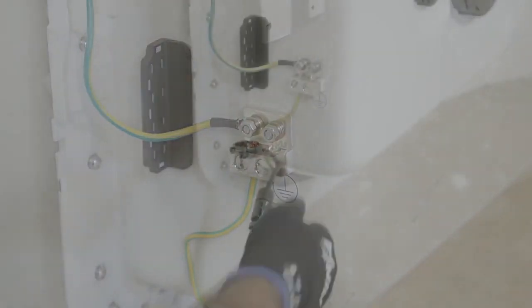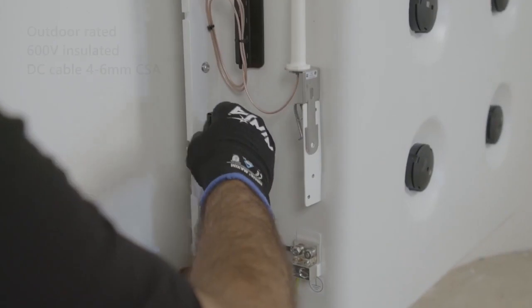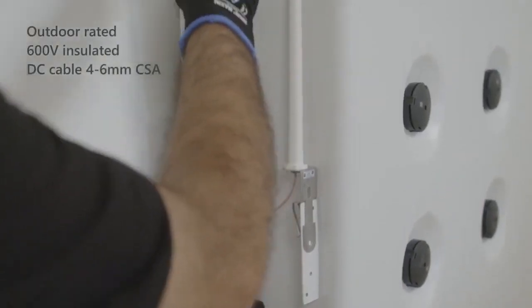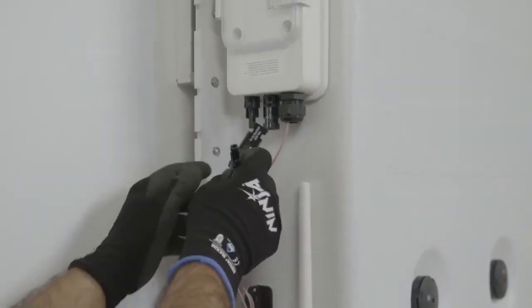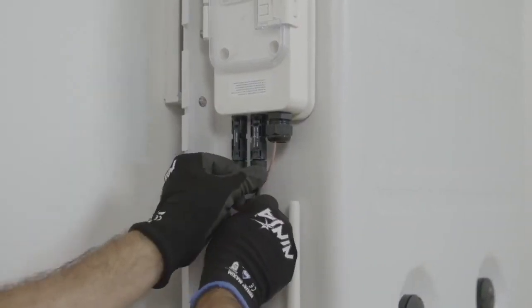Once the earth is in we can then fix the DC. With the battery comes supplied two MC4 connections, so simply connect those to suitable PV DC 600 volt rated cable and connect them into the positive and negative associated terminals.